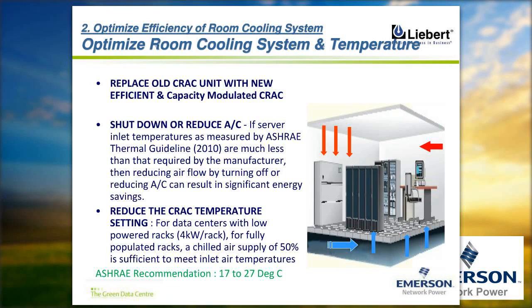Now, in data centers which are hardly a couple of years old, when the temperature at the server inlet was maintained at 17-18 degrees, the temperature leaving the precision AC system used to be around 13-14 degrees. So there used to be a huge amount of loss to maintain such a low temperature, which was never desired. So now I would recommend setting a temperature point of 22 plus minus 1, and that would suffice, not only for operational requirements and performance but also to help reduce consumption. There are customers in India who are now evaluating if they can keep 24 degrees as well. That's how one can think of reducing energy consumption further.